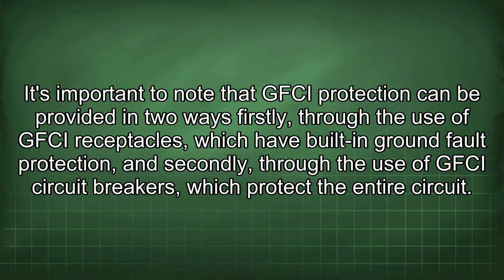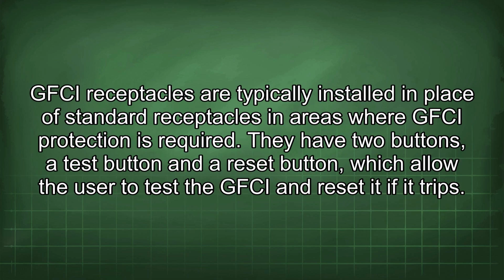It's important to note that GFCI protection can be provided in two ways. Firstly, through the use of GFCI receptacles, which have built-in ground fault protection, and secondly, through the use of GFCI circuit breakers, which protect the entire circuit. GFCI receptacles are typically installed in place of standard receptacles in areas where GFCI protection is required. They have two buttons, a test button and a reset button, which allow the user to test the GFCI and reset it if it trips.